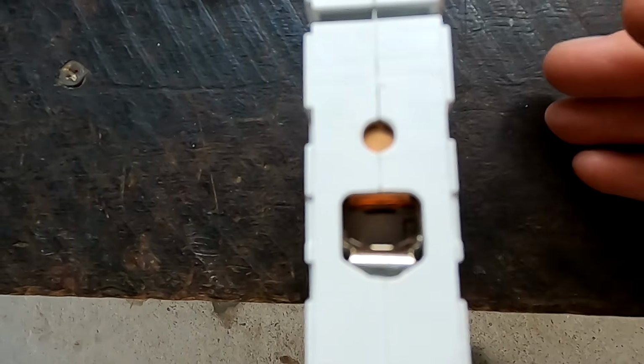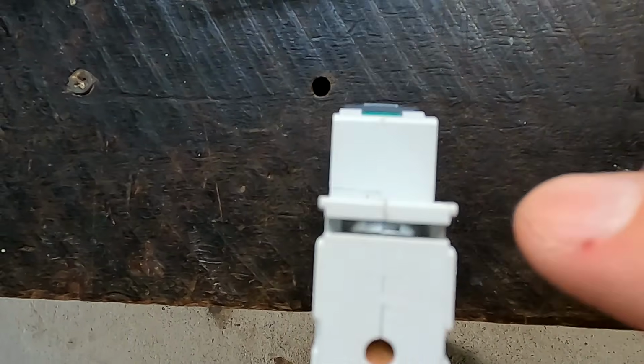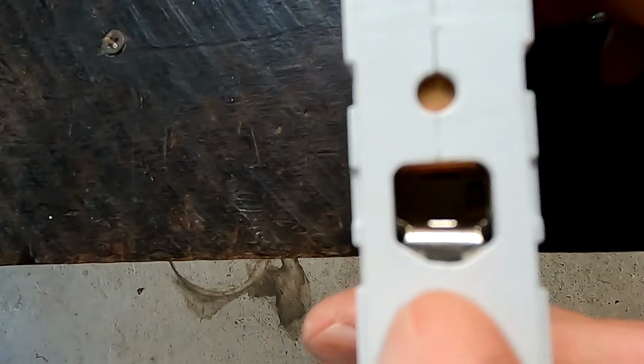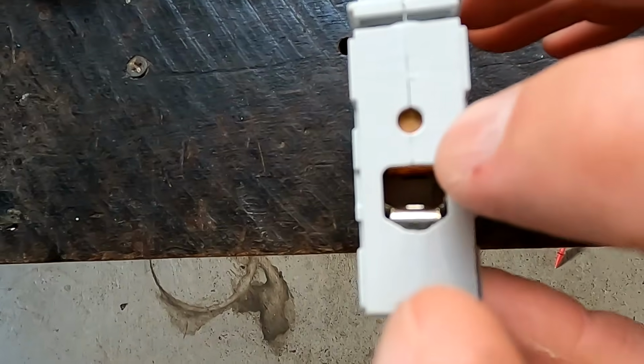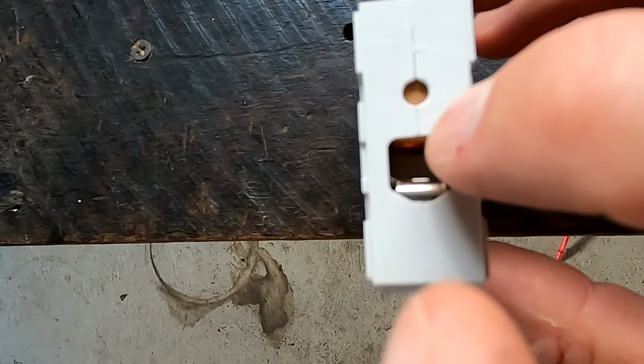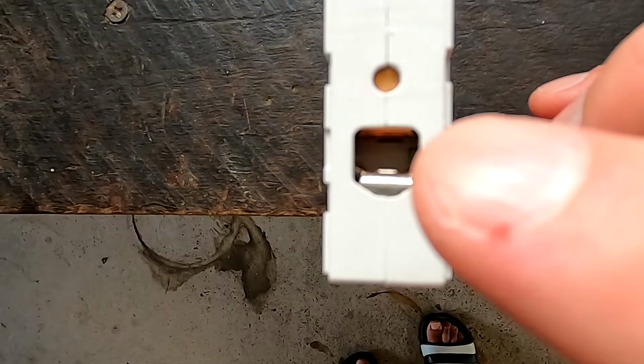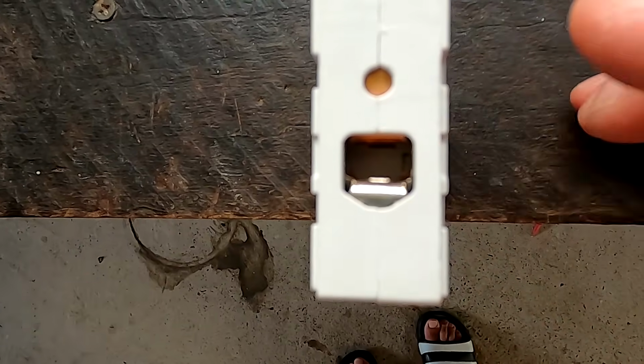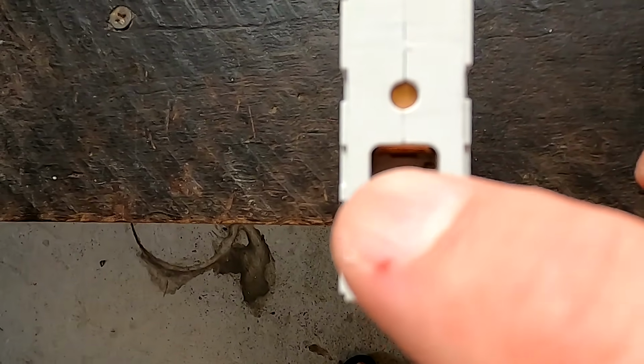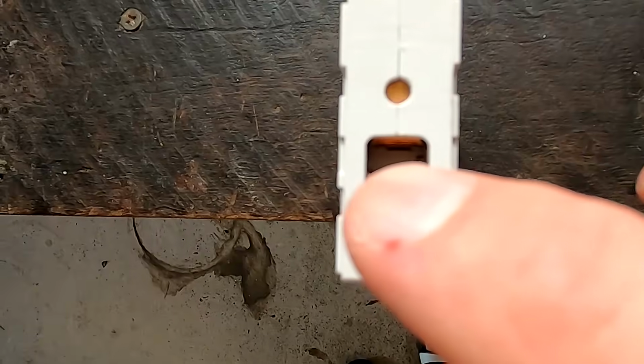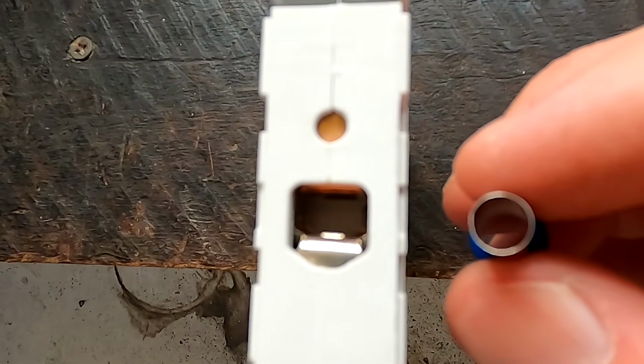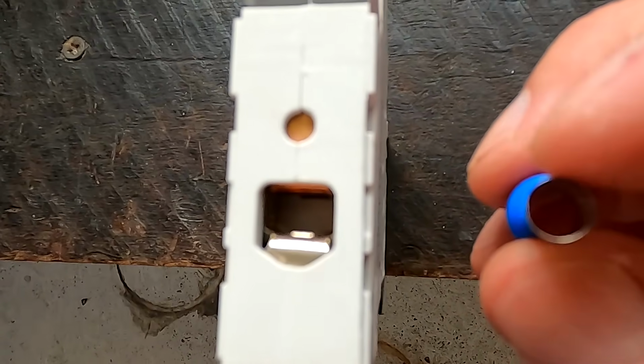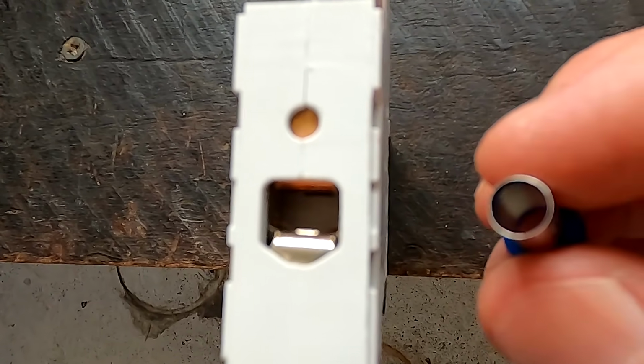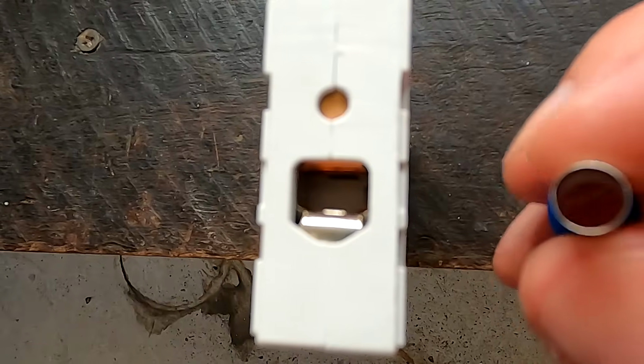And do not ever have the idea to solder your cable before you put it into one of these terminals here, because then you have a solid, stiff, round cable, and it will touch the actual contact of your circuit breaker only at the top. And this could cause a lot of heat because of the very limited contact area then. Never ever solder these stranded cables.